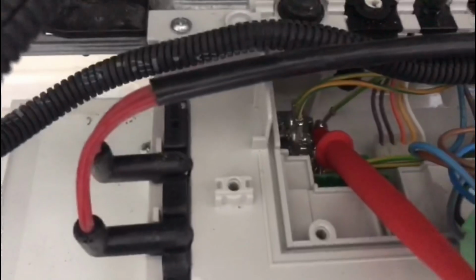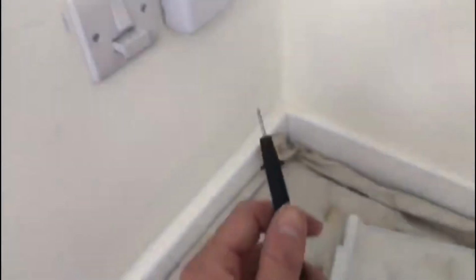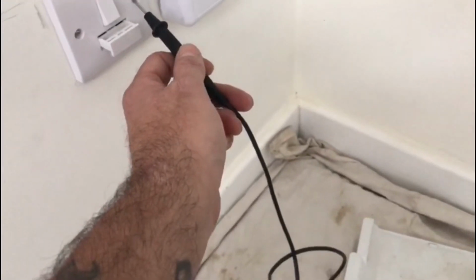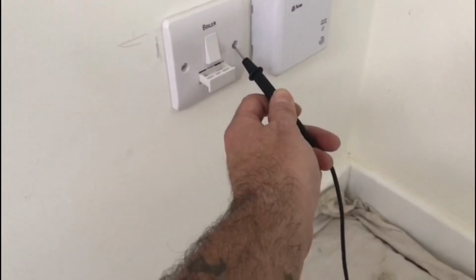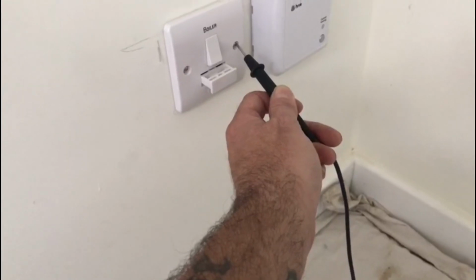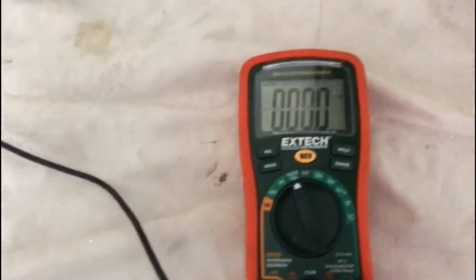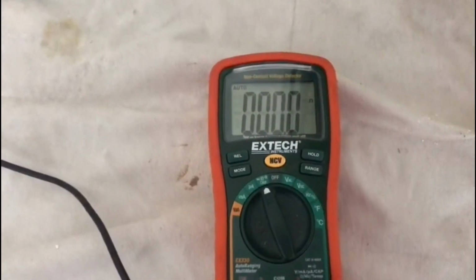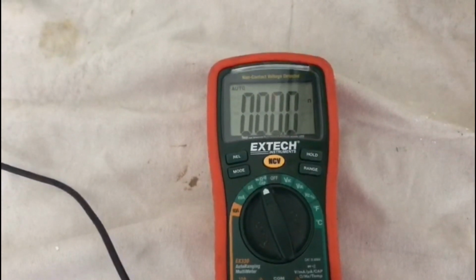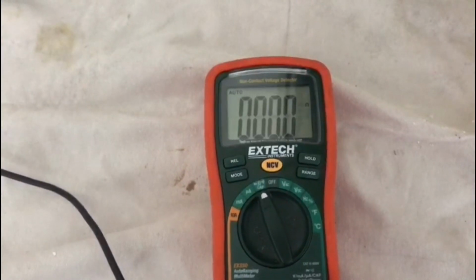Okay, testing earth continuity of the boiler. I've put my probe in there on the earthing bar. I'm going to go to my socket screw of my fuse spur and check the readings on my multimeter. As you can see, it's showing 0 ohms continuity.